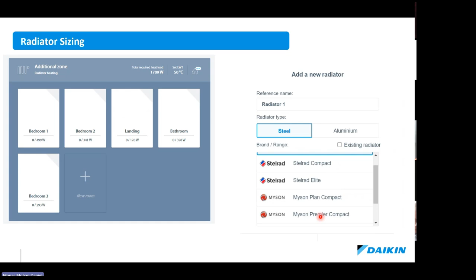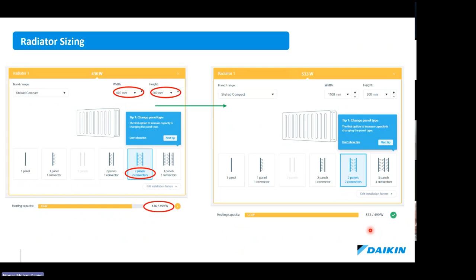So if we take a look at an example here, radiator 1, the required heat loss is 499 watts, and this is a Stelrad compact. So you have the dimensions of the radiator over here, which you can modify, and the type of panel. So if it's a 2-panel, 2-convector, you keep increasing the width to get the required output. Over here, if you see, a 5 by 1.1 gives 533 watts, which is sufficient for that room. And likewise, you would complete it for all of your other rooms in the property.